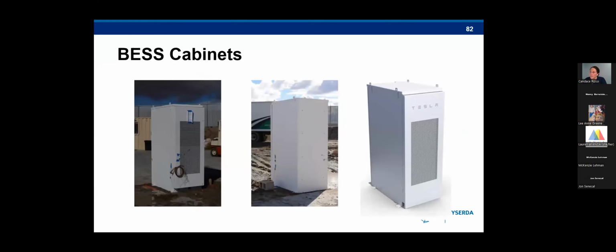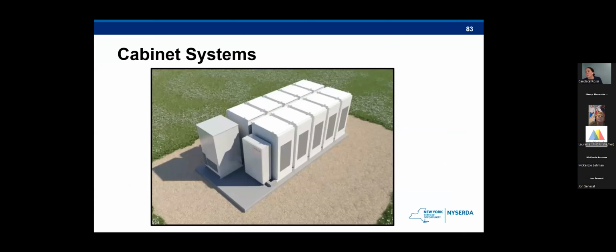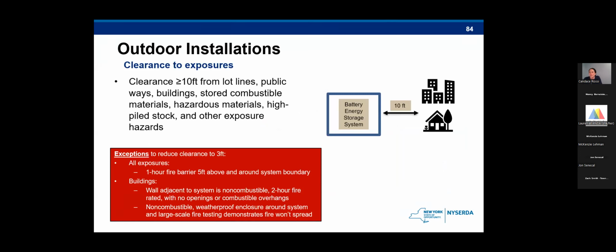And here, this is an example of some of the energy storage cabinets that house batteries that can be installed outside. And here's just another one as well, an outdoor cabinet system. This can also show you how size and separation compliance isn't required when the system is considered remote. And then for outdoor installations, we have requirements to talk through that are only required for them.